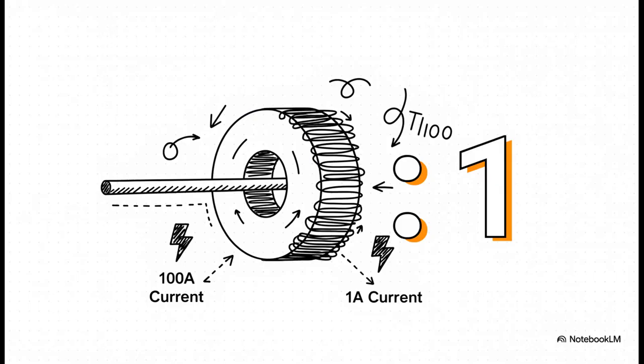Now, what's really interesting is the math, specifically the transformation ratio. This is where the actual translation happens. Imagine your primary has just one turn, like that main cable passing straight through the hole. Now say your secondary coil has 100 turns of fine wire. Mathematically, a huge 100-amp current in the primary shrinks all the way down to a perfectly safe 1 amp in the secondary. All that heavy lifting, done purely by the math of those turns.